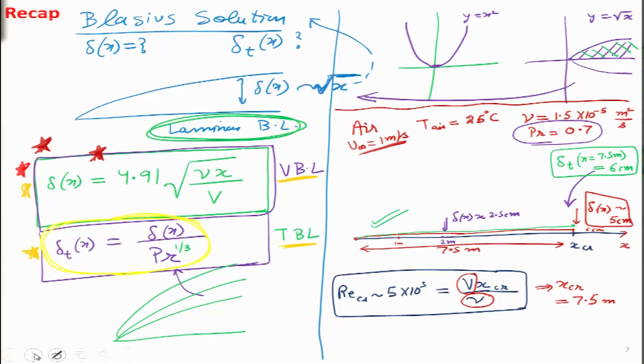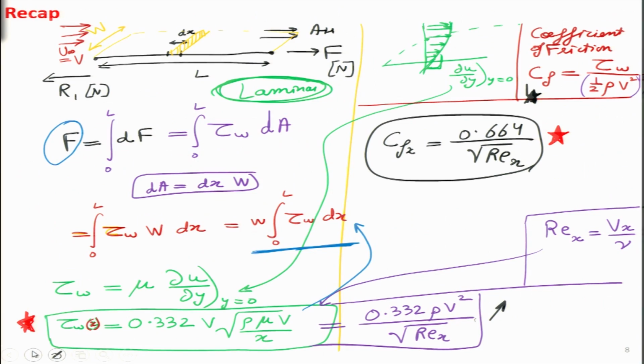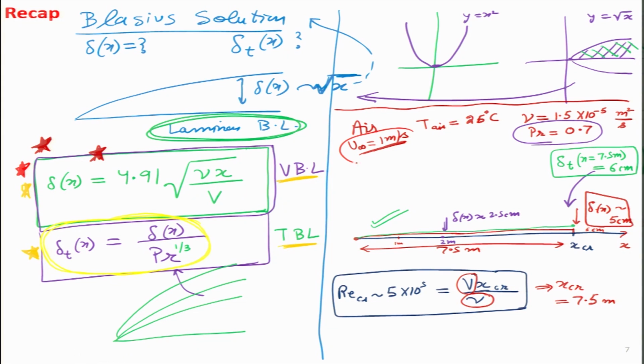It is not very large, but very small. After 7.5 meters, that boundary layer had become about, I think, 5 centimeters or 2 inches. So, it is very small, if 7.5 meters is almost the width of this particular room. So, across the whole room, the width of that boundary layer was 2 inches. Of course, we kept the velocity low. If we remember in this simulation, we have kept it as 1 meter per second. So, it is a function of velocity as well. If I increase the velocity, then the boundary layer will become smaller and smaller. So, it is very interesting.